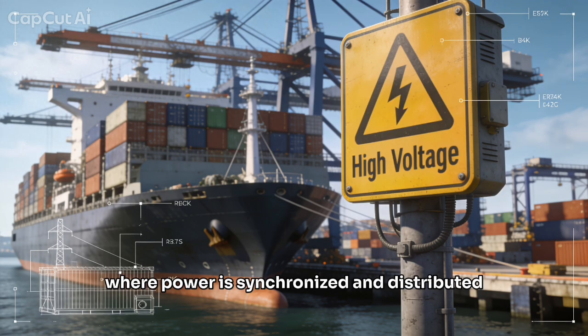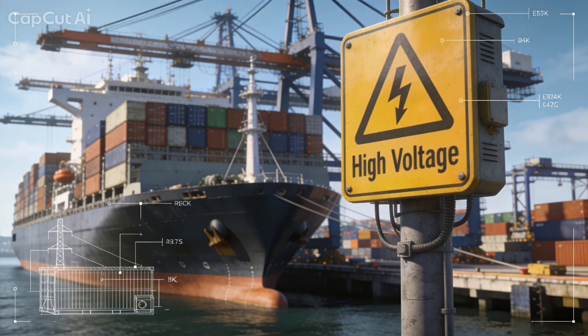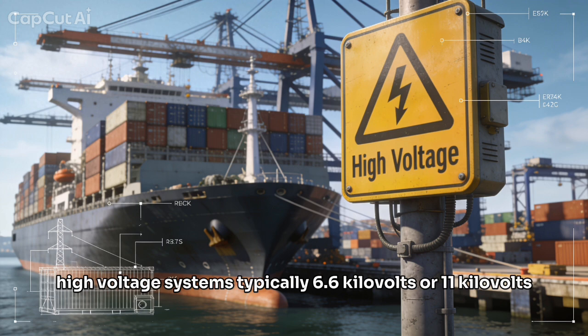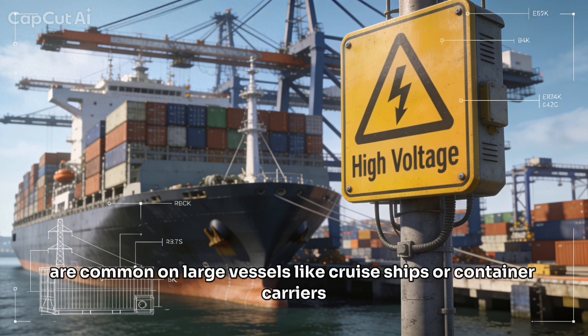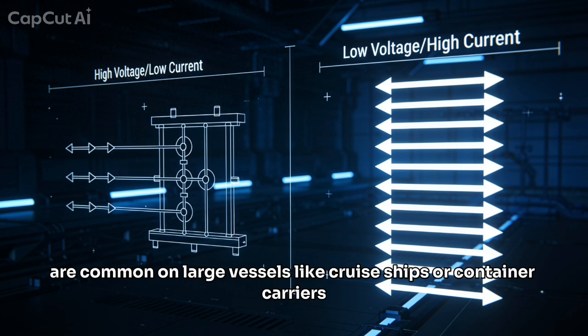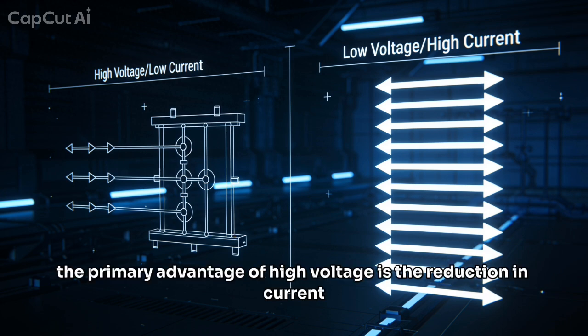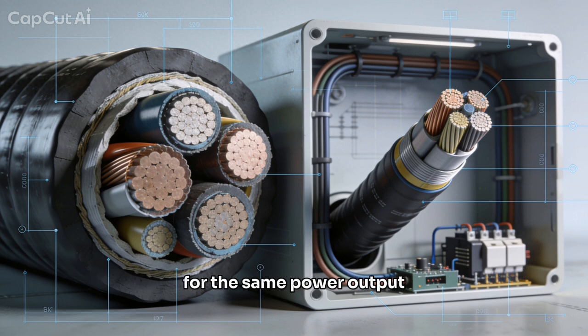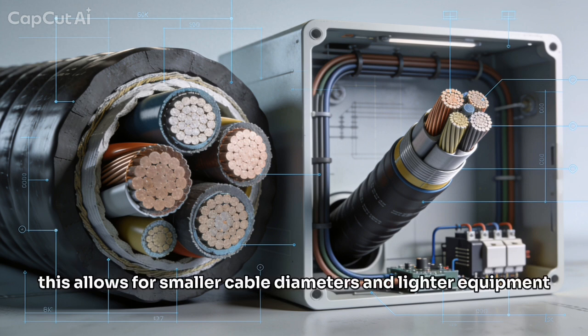High voltage systems, typically 6.6 kilovolts or 11 kilovolts, are common on large vessels like cruise ships or container carriers. The primary advantage of high voltage is the reduction in current for the same power output. This allows for smaller cable diameters and lighter equipment, saving significant space and weight.